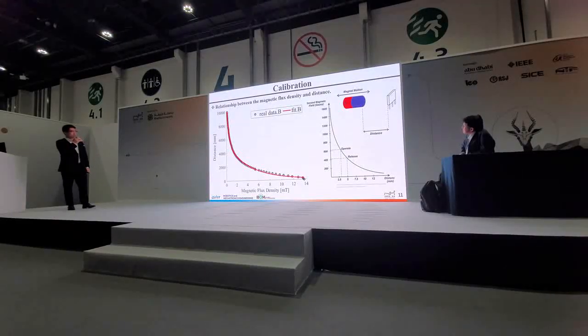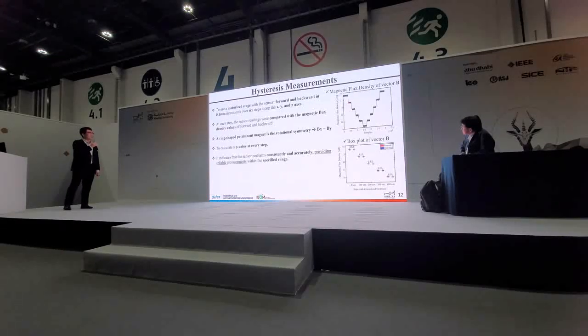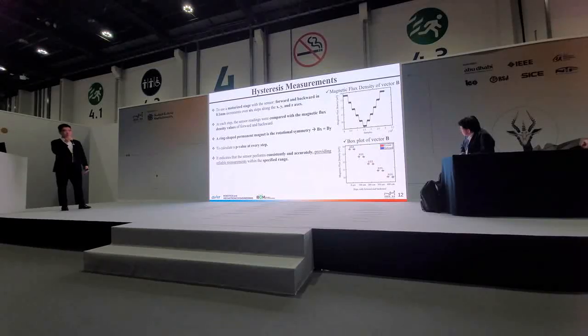Let's move on to calibration part. Relationship between the magnetic flux density and distance is measured in real environment, and this plot can explain the tendency of distance and magnetic flux density. Let's see the hysteresis measurement. We utilize a motorized stage moving the sensor forward and backward in 0.1 millimeter increment over 6 steps along X, Y, and Z axis. At each step, the sensor reading were compared with the magnetic flux density value of forward and backward.